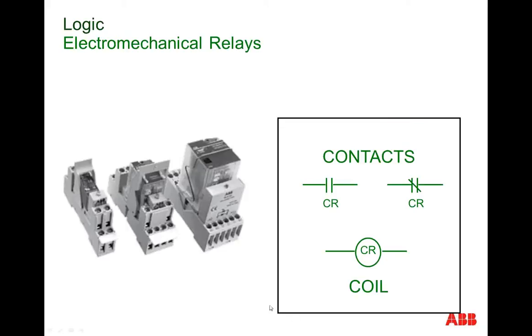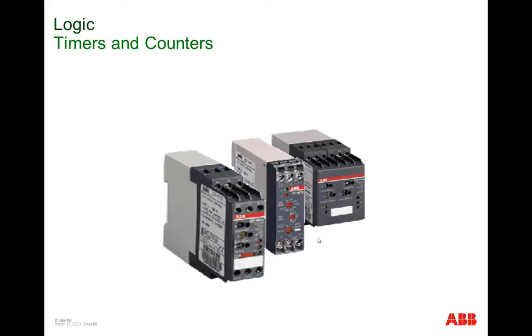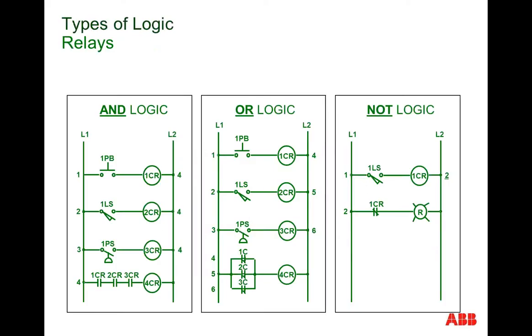Now, electromechanical relays are like the contactors we talked about, but they don't start and stop electric motors. They have normally open or normally closed contacts, and they have a coil. So when I energize the coil of the relay, I can either open or close contacts at will. And as I wire these in patterns, I can form different patterns of what we call Boolean logic. Now, sometimes a relay also has a delay built in, and that's called a timer. Another form of a relay might count the number of pulses, or the number of times I close its coil, and stores those numbers. That's called a counter, or it's another form of a relay that's counting production.